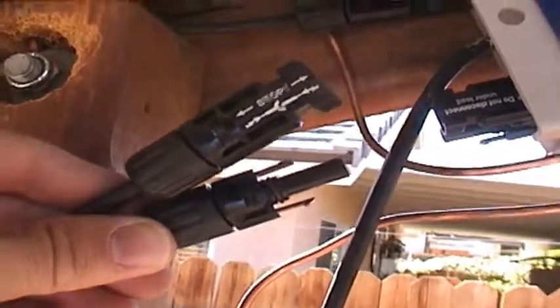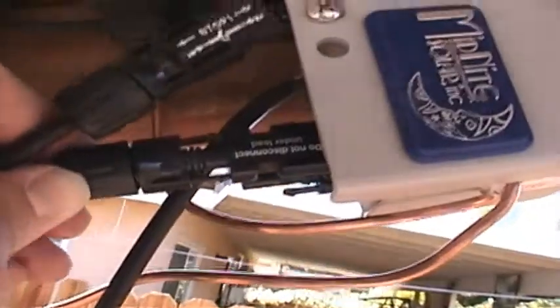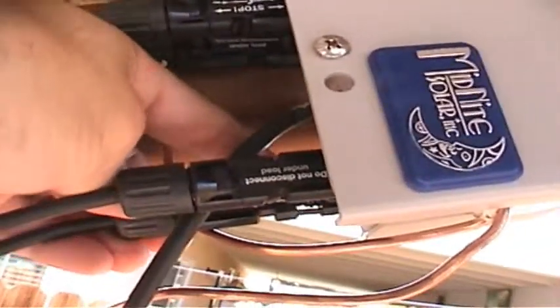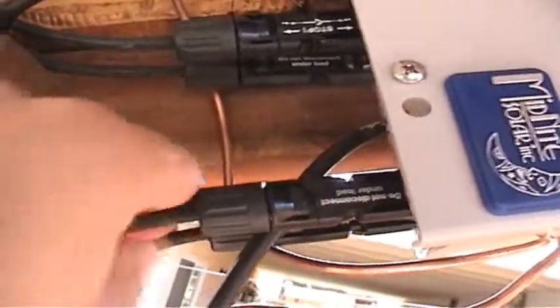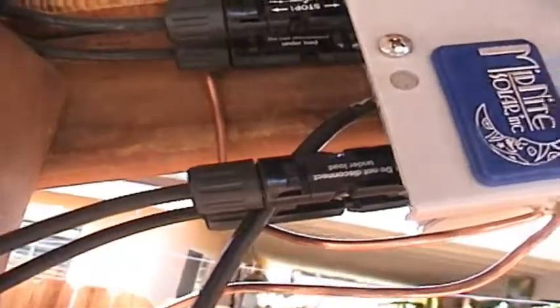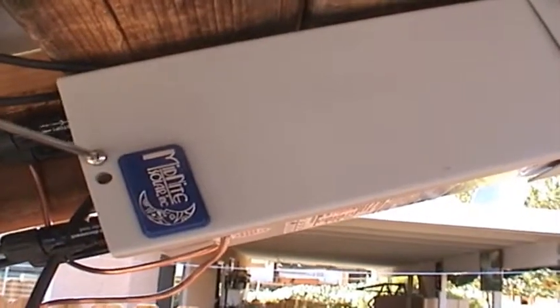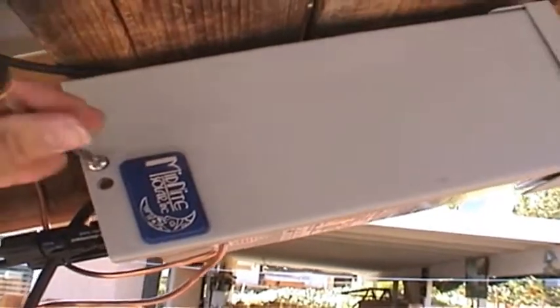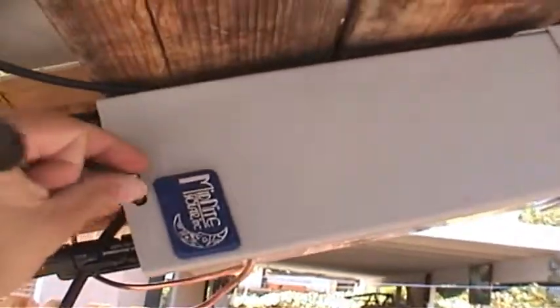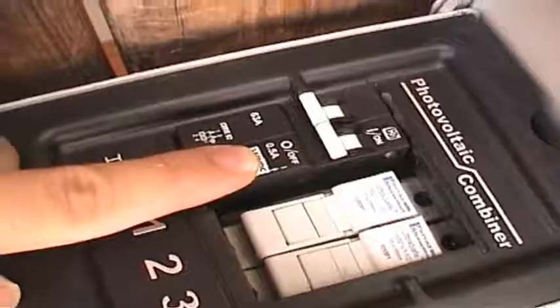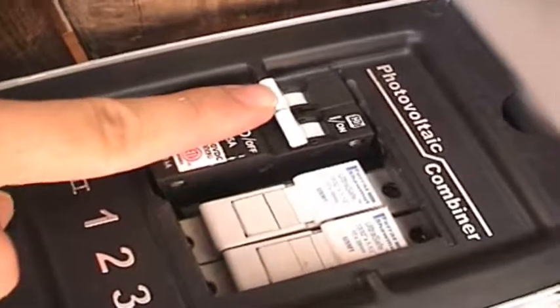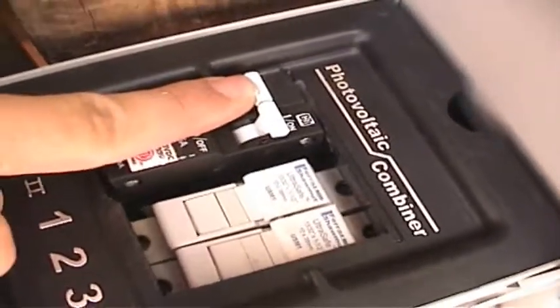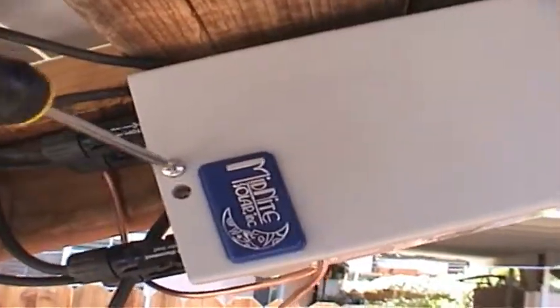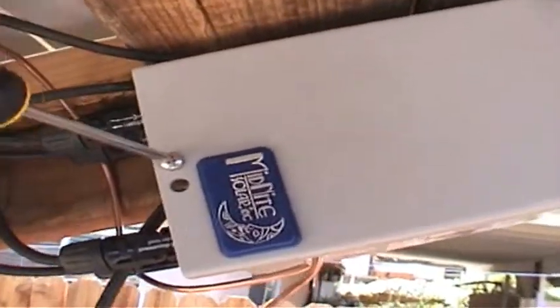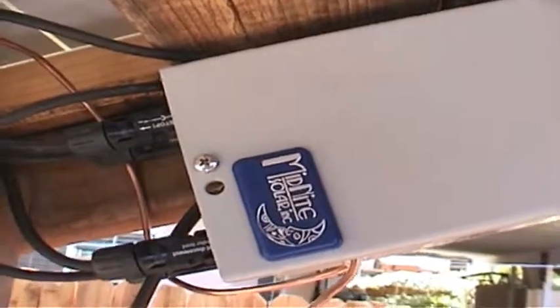Then we'll grab the connectors from the second solar panel, plug them in to the combiner box. Again, make sure they're nice and tight. Now there is a very good chance that the GFP device in the combiner box is in the off position, so let's go ahead and open the front panel and take a look. Sure enough, it is in the off position. Let's go ahead and flip it to the on position. And let's close our combiner box. And then replace the front cover screw. Okay, let's head back into the garage.